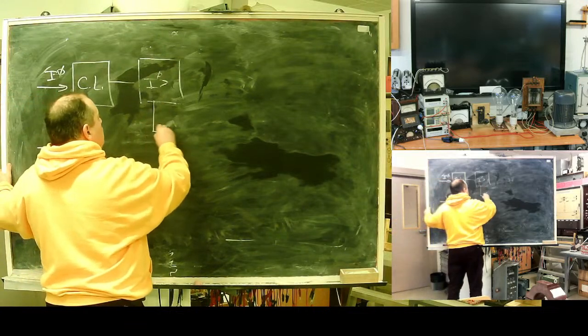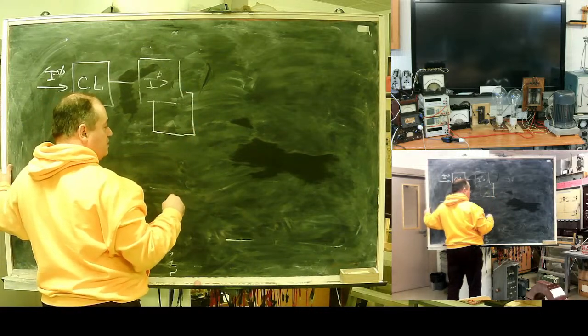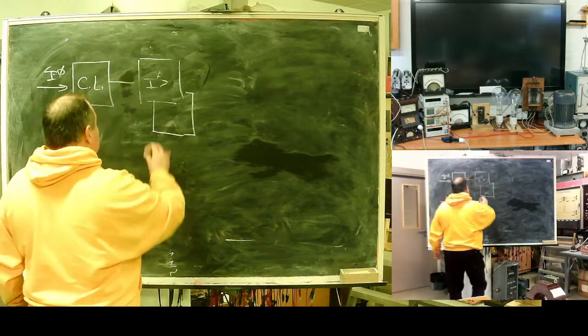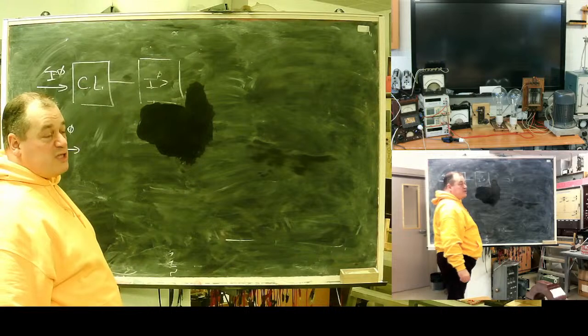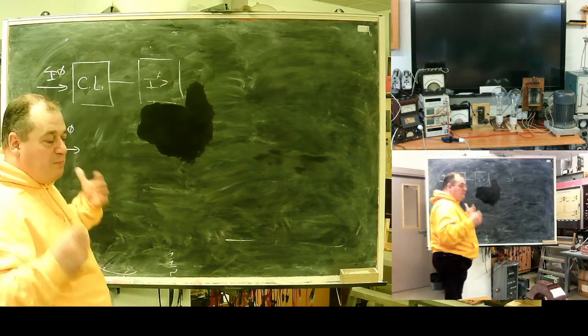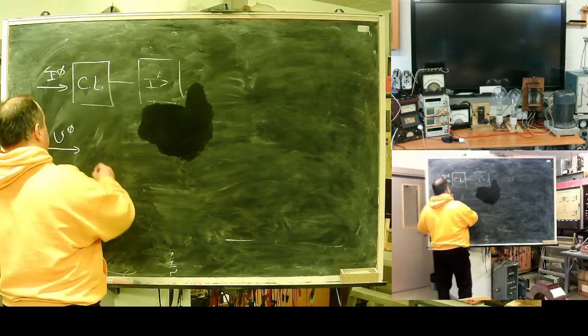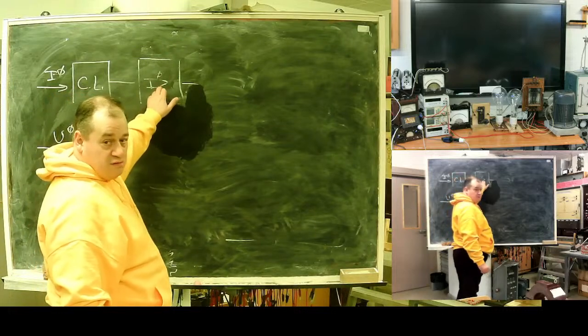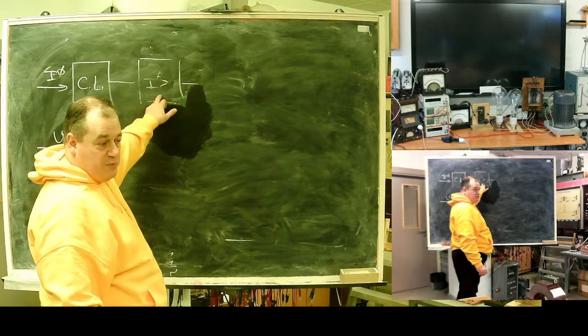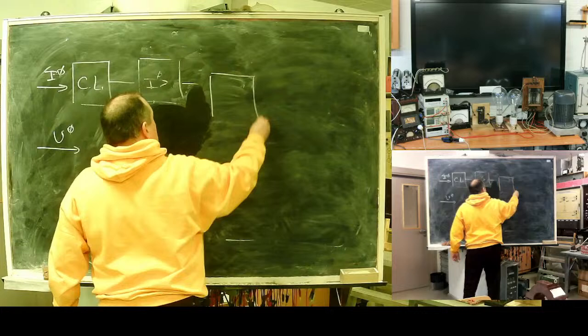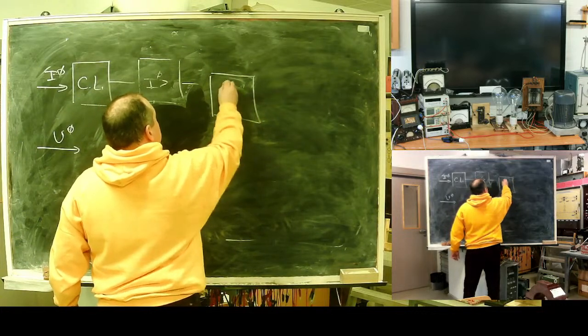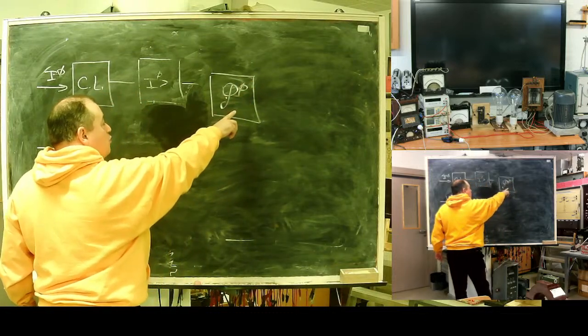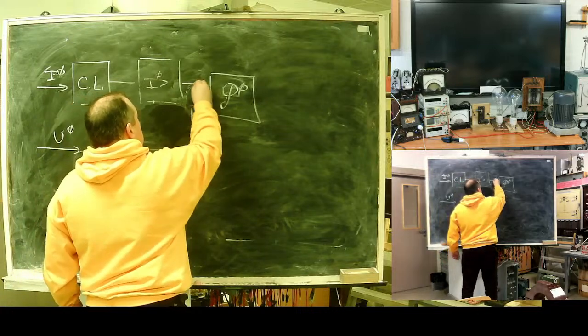For example, can have two stages, but actually one is enough, because current again, healthy part of network determines this current. Multiple stages are absolutely redundant. The only, in third time, role of this element is to prevent false operation from network non-symmetry. Characteristic, angular characteristic. Angle between zero sequence current and zero sequence voltage.